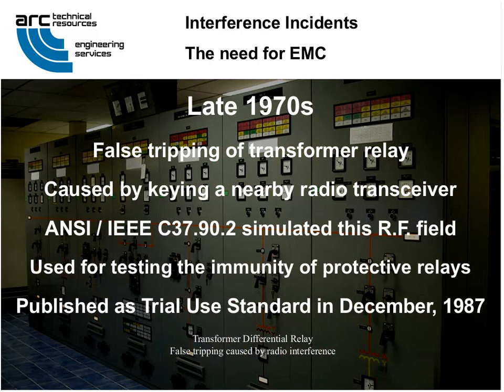In the late 1970s, the false tripping of a transformer differential protective relay knocked a 380 megawatt steam turbine generator offline. It was caused by an employee keying a portable radio transceiver less than 1 meter from a protective relay rack. The story I heard was he had the radio in his back pocket and he was leaned over and he just backed into the thing and keyed it against the cabinet. Well, that brought it off.